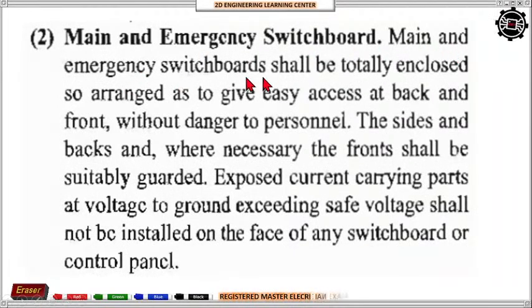So main and emergency switchboard shall be totally enclosed. So arranged as to give easy access at the back and front without danger to personnel. So enclosed siya pero pwedeng ma-access yung likod o yung harap, na hindi naman ma-endanger yung nagmi-maintain na electrician or technician. The sides and the backs and where necessary the front shall be suitably guarded. Exposed current carrying parts at voltage to ground exceeding safe voltage, yung safe voltage dito is 50 volts below, shall not be installed on the face of any switchboards or control panel.